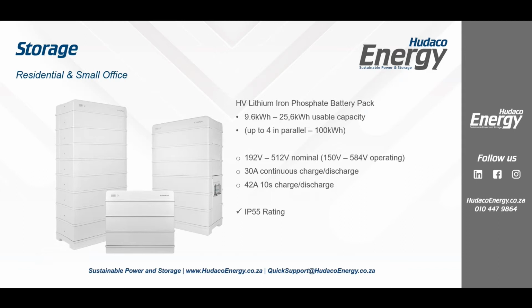Okay, here we've got 1, 2, 3, 4, 5, 6. So this battery bank is the biggest one that we can put on the single phase unit, and this battery bank is the biggest one that we could put on a 10 kilowatt 3-phase unit. You'll notice we're only doing training on the single phase. The 10 kilowatt units, there's just no stock, so we're not even going to focus on those until next year again. Okay, so anywhere from 3 to 6 in the stack. Okay, need compact. The entire time to assemble this entire battery bank is about 2 minutes per cell. So 1, 2, 3, 4, 5, 6. So that's about 12 minutes, maybe 3 or 4 minutes to do this part. And then the longest part is actually just putting the cables and connecting the cables in. Your entire commissioning, from unpacking your boxes to commissioning of the battery and inverter, is approximately 1 hour.